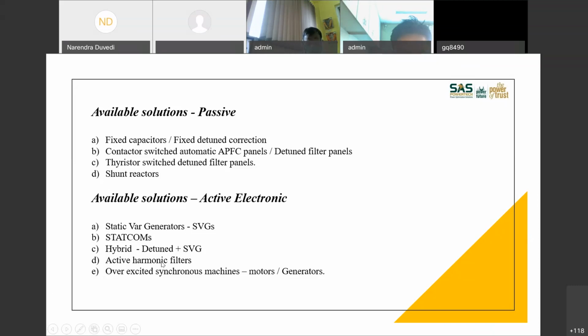You get active harmonic filters. All of us mostly know that these things exist. This question comes quite often, so I'll explain the difference between SVG and STATCOM here. SVG can deliver only lagging or leading reactive power. SVG cannot typically correct harmonic distortion, whereas the current capacity of a STATCOM can be programmed between harmonic correction and reactive power compensation. So this is the basic difference between these two.